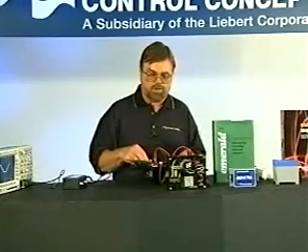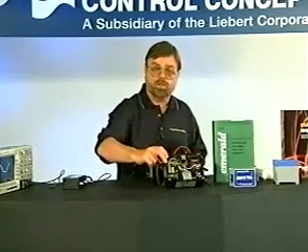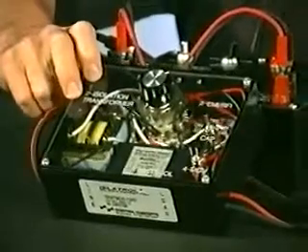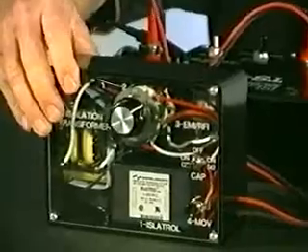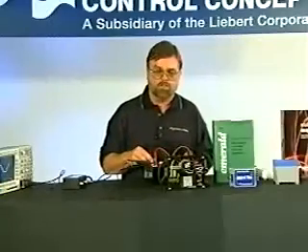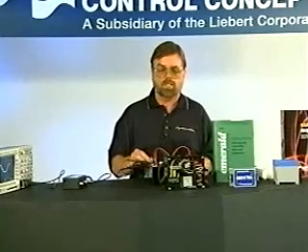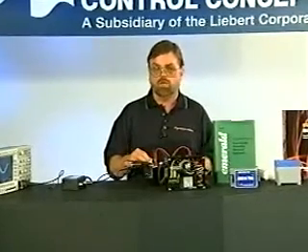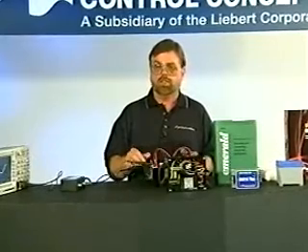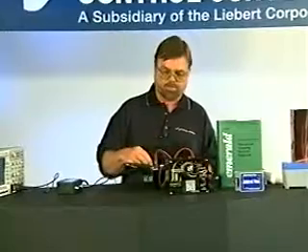I'm putting these spikes on the sine wave through this test box, which represents the various technologies available in the market today. The first position, or position 4 here, is a metal oxide varistor, or MOV for short, which is a surge clamping component or surge clamping technology. Basically, the way an MOV works, it's wired around the power line and does nothing unless it sees a very high voltage transient, in which case it clamps it.